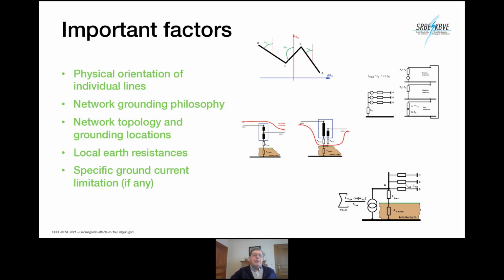The second point is the network concept of grounding the network. In high voltage, it is practice to have a grounding principle. You have to select it from the beginning and you have to maintain it, because it is the basis of all the design of the network, the basis of the high voltage insulation, of fault current detection, and so on.